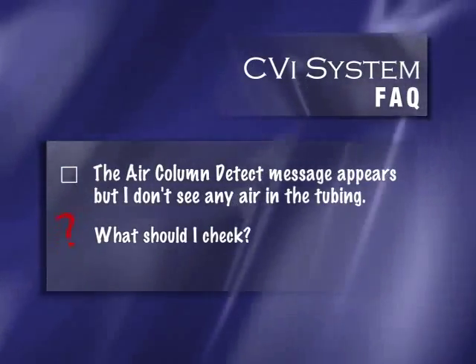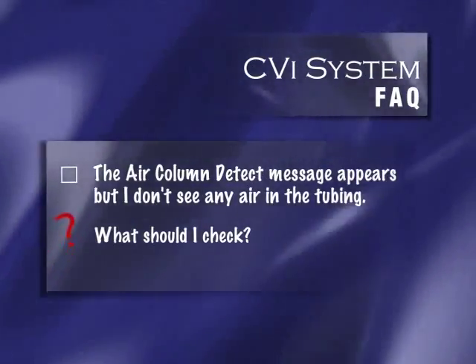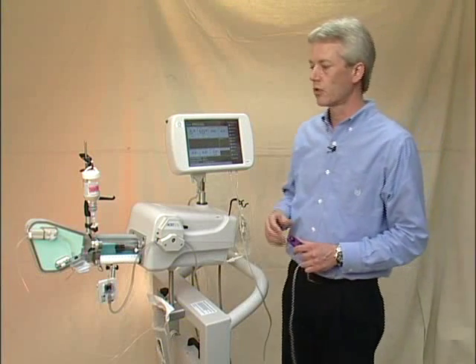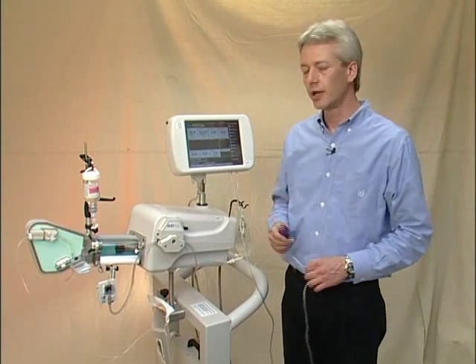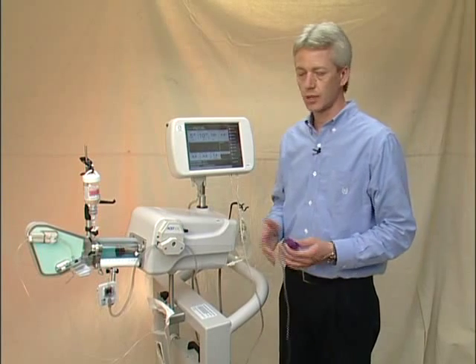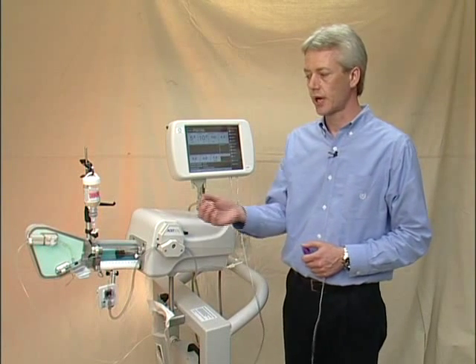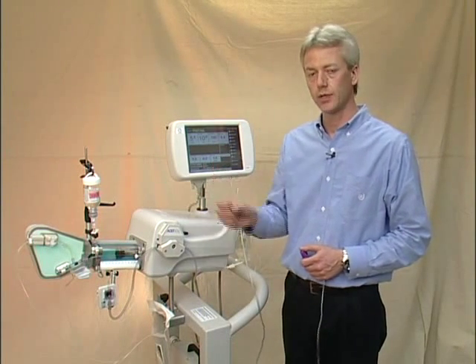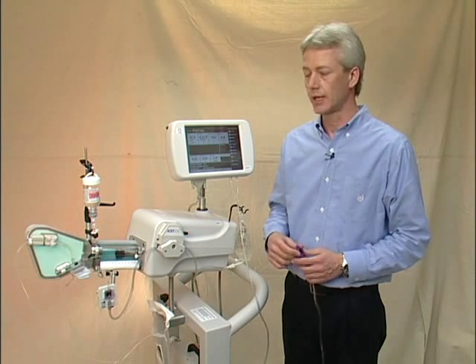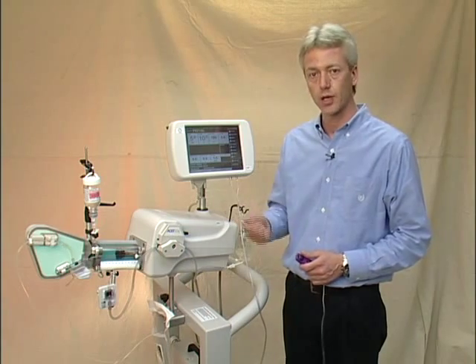I keep getting an air column detector warning, and there's no air in the tubing. Air column detector warnings are not an error message, it's an informational message. Sometimes it's as simple as the contrast tubing is not clipped into the sensor properly, and sometimes it may be the strain relief is also not engaged to prevent any false tugging on the sensor.